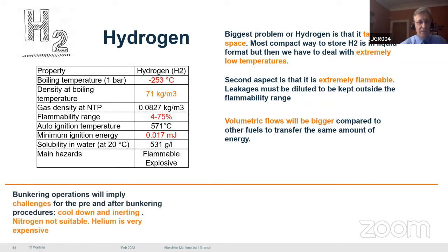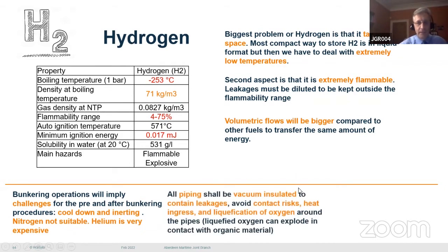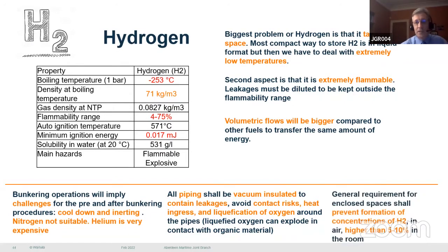Bunkering operations would imply challenges for the pre- and after-bunkering procedure. In terms of cool-down and inerting, nitrogen wouldn't be suitable. Helium would be, but it's a rather expensive medium. Again, the piping should be vacuum-insulated to contain leakages, avoid contact risks, heat ingress, and the liquefaction of oxygen around those pipes, since liquefied oxygen can explode under those conditions with organic material. Generally, for the enclosed space, the concentration has to be dealt with appropriately to prevent the formation of, say, 5 to 10% in that room.